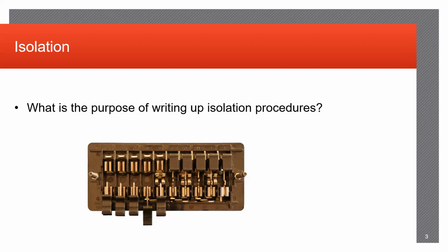So in this application specifically, when we're going to test a relay, we need to isolate the relay thoroughly to ensure that while testing, we don't accidentally cause a misoperation of any in-service equipment in the substation itself, as well as avoiding any form of inrush current or voltage sources to any other pieces of control house equipment that other personnel may be working on.